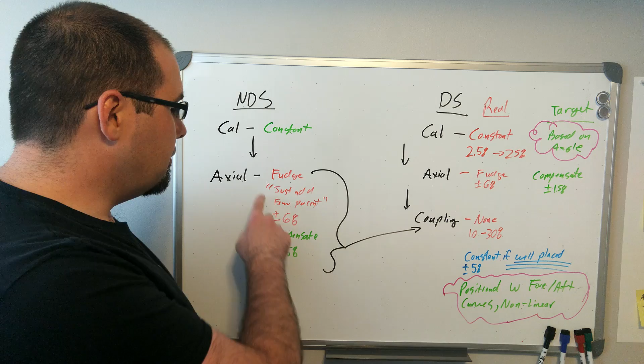So we have to start with the non-drive side. And as I've mentioned many times, there are two methods of dealing with this. If you have a single bending arrangement, like many of the products out there, especially all of the Chinese-based clones, well, then you have a constant calibration factor, but you have a fudge factor. Essentially that fudge factor is to take out, if you put in a lot of axial force, it will read low. And so they just dial those up a bit.